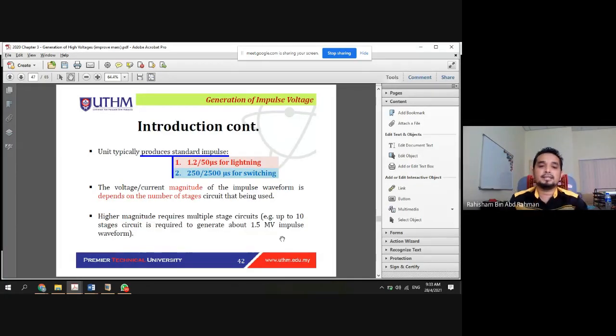There are two main categories, as I explained earlier: one for lightning, one for switching. These are not the only ones; there are other impulse waveforms, but these are the most commonly considered for high voltage applications, for the reasons I just explained. The difference here, for example, for the standard, is 1.2/50 microsecond.